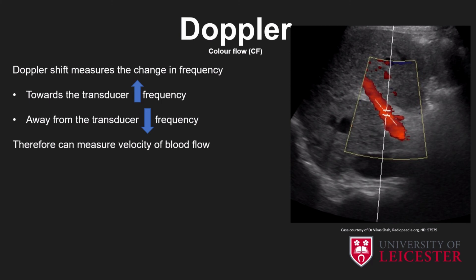Just to note, because it's commonly assumed, the colour scheme has no connection to arterial and venous blood flow. It is because it's moving either towards the transducer with a high frequency or moving away from the transducer with a low frequency. And the colour can actually be interchangeable. The magnitude of that change is the Doppler shift.